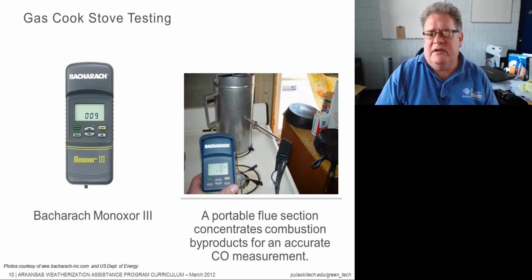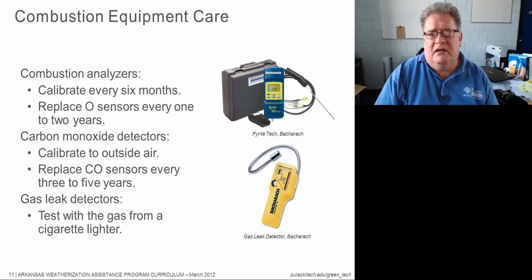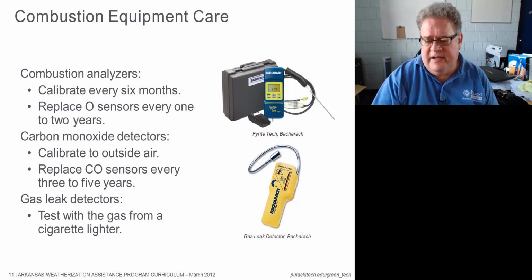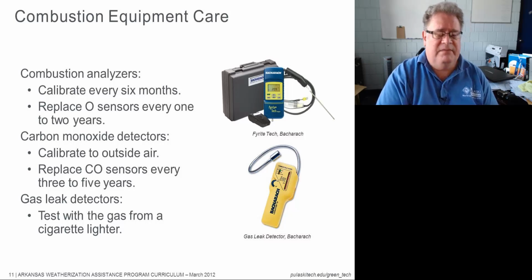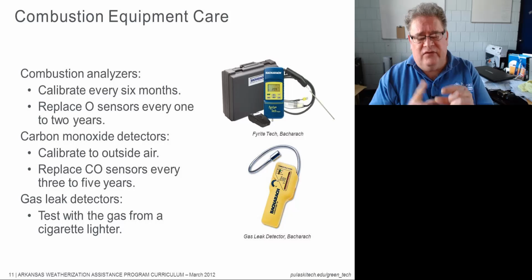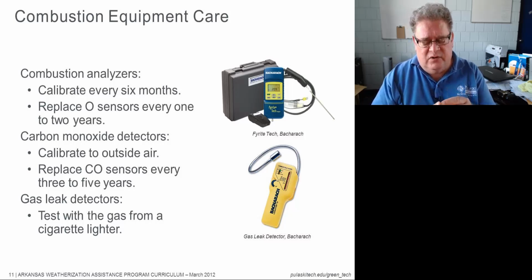Taking care of your equipment, especially combustion equipment, can be a little bit of a pain. If you don't know how often to calibrate it, the manufacturer doesn't say. Some of them need to be calibrated every 6 months. They need to have the oxygen sensor replaced every 1 to 2 years. They're generally shipped in sealed packages, if they're field replaceable.